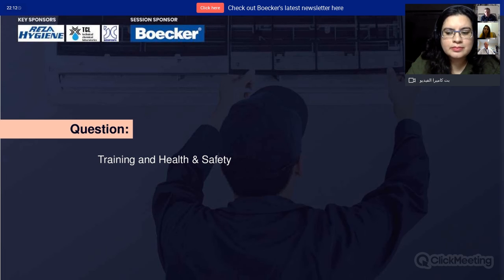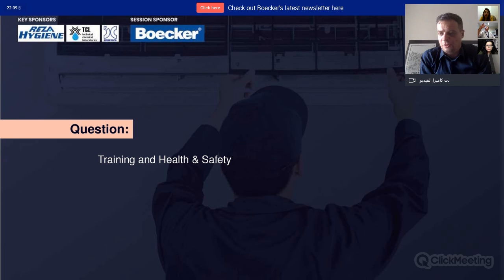A heat recovery wheel is a component of an air handling unit used for keeping humidity levels and using the thermal energy of the exhaust air mixing with the intake air in order to save energy. These components are there for a reason. We do not recommend switching them off, and I wouldn't be concerned about cross-contamination because of the heat recovery wheel, specifically if we're talking about recirculation anyway. So before being concerned about heat recovery wheels, I'd be more concerned about whether I have a filtration stage at the recirculated air.